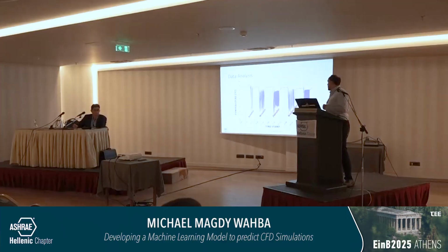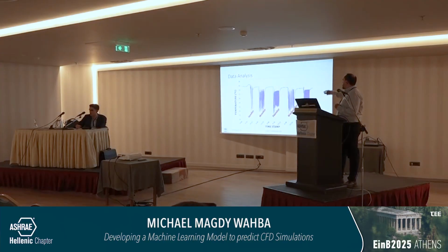Here's the temperature validation of the model. You can see the change of temperature from the supply at the beginning of the day. Here the temperature is decreasing because this was put at the inlet or supply of the HVAC. So you can see exactly how the zone temperature supply is changing, and this was used for the validation.